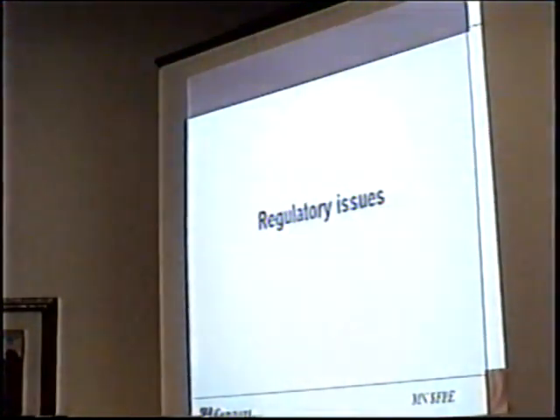I've been told that when people guesstimate what the lower leakage split is, it's more of a European practice, or at least for jurisdictions under ISO 14520. In that code, they limit you to a value that has to be above 0.15 or less than 0.5. NFPA doesn't have any requirement or limitation. In fact, there's no reason that it couldn't be above 0.5. All of the mathematics work out beautifully for it. As I showed you in one diagram, if the flow is choked at the top or the floor, essentially the flow is less.